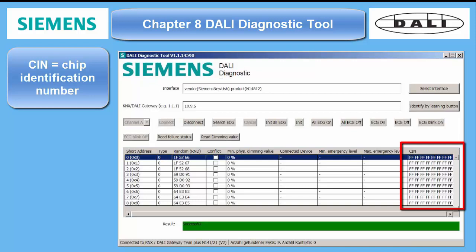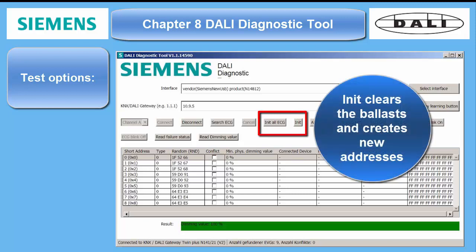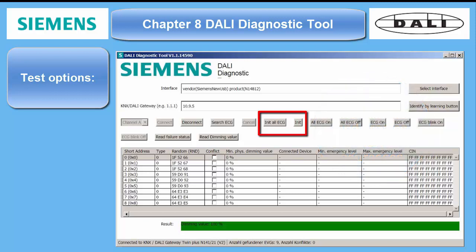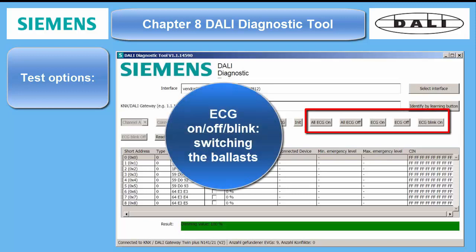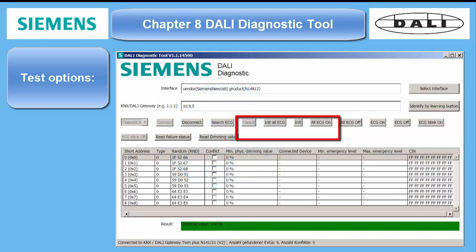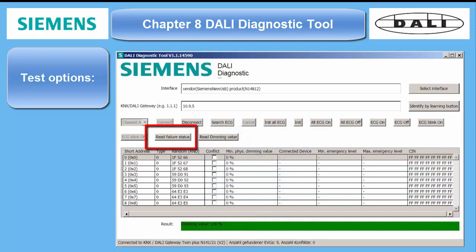So here there are no codes visible, beside all digits being on FF. Test options: Init — init all ECG — clears the ballast's memory and assigns randomized new addresses. This is used to get rid of conflicts caused by duplicate short addresses. ECG all on, off, ECG blink — self-explanatory. Read failure status returns the present condition of ECGs: lamp on, off, or invalid condition. Read dimming value — self-explanatory.